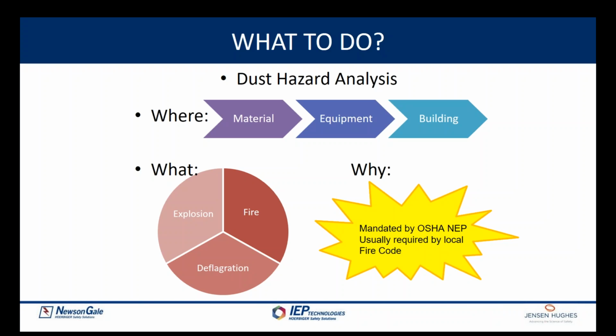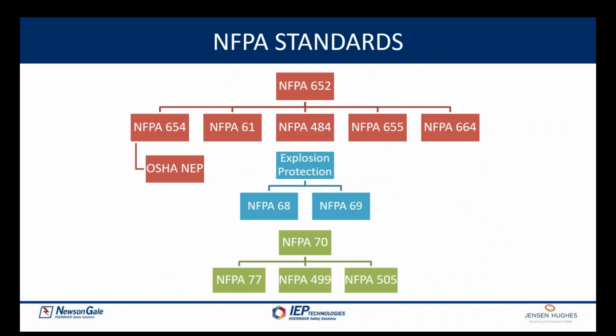Interestingly, we should all be aware and know that there is a mandatory retroactive requirement in all of the occupancy-specific NFPA standards. These are not code, but they're frequently adopted by code, and therefore they do become regulatory requirements. The NFPA standards actually represent what you could call good engineering practice, primarily in North America, but these standards are also used internationally and in Canada. This graphic shows the hierarchical relationship among the various primary standards that are mainly applicable to combustible dust occupancies.